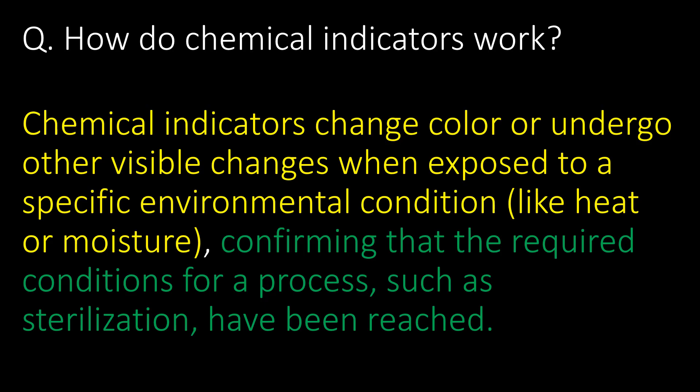A basic and important question: how do chemical indicators work? Chemical indicators change color or undergo other visible changes when exposed to specific environmental conditions like heat or moisture, confirming that the required conditions for a process such as sterilization have been reached.